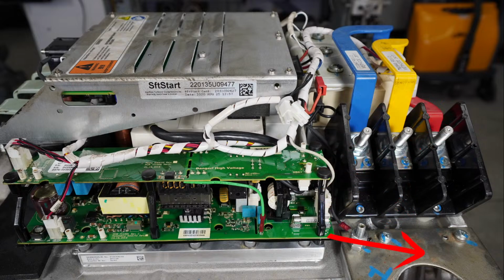So, are you getting power into the compressor, feeding the fuses, and obviously this one doesn't, or do you have a blown fuse somewhere? Any of those things are going to cause a scenario where it may not be powering up. So let's first chase down, okay, we verified our fuses are good and we have power up here to the fuses.